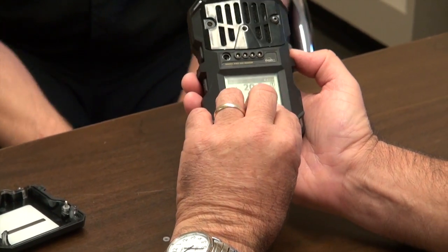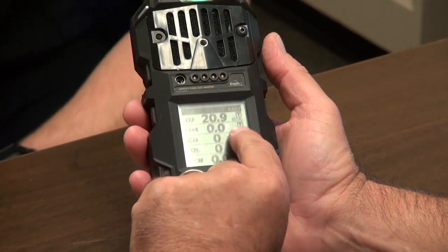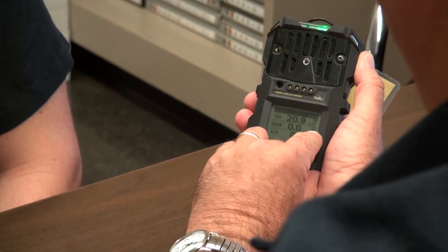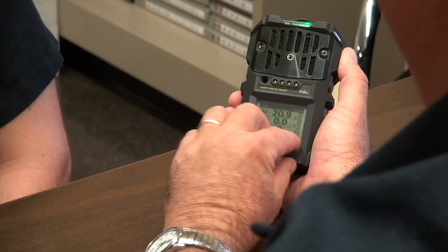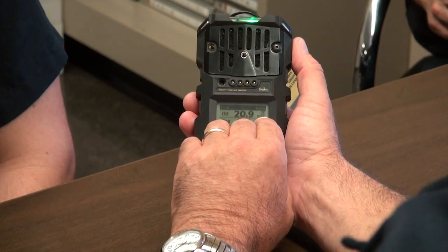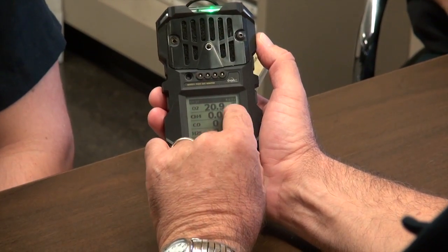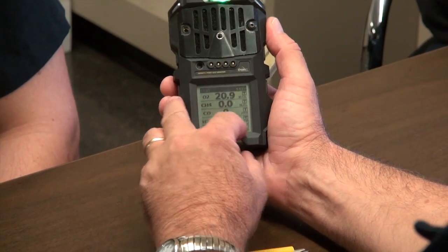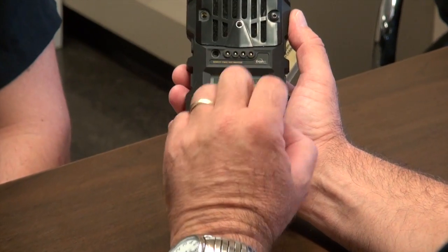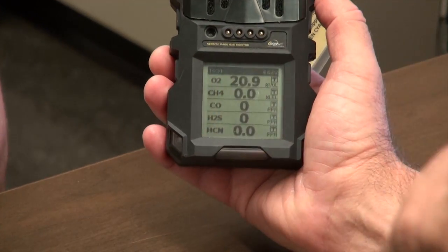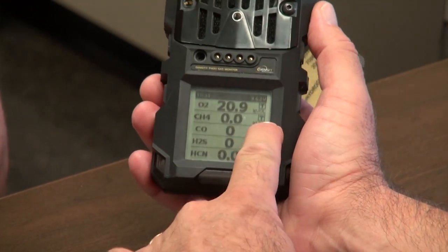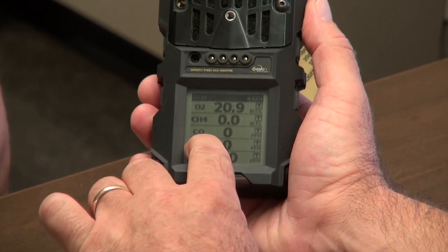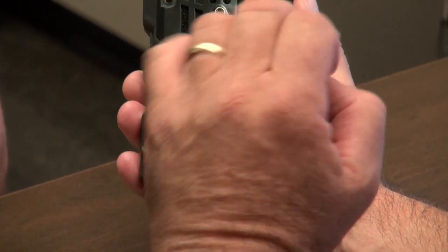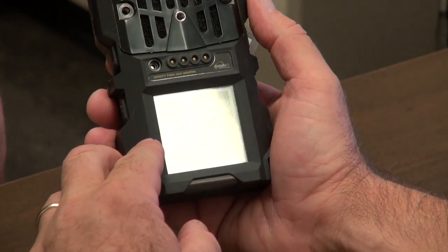The far right side, beside your percentages, there's a T. Under the T, it'll tell you percentage of LELs, parts per million. What that does is give you a heads up. Once you start getting into a product, it will start flashing just to give you a heads up that you're getting into something. Once it reaches 100%, your lower LEL will go into an alarm. So it's just a heads up, immediate detection to let you know something's going on.